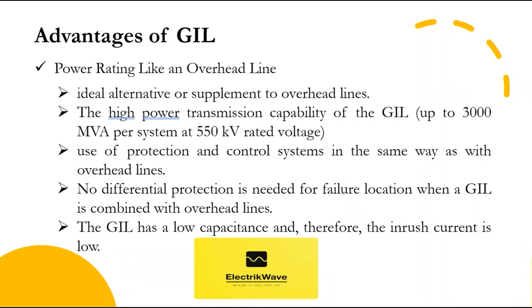GIL has power rating like an overhead line. The GIL is the ideal alternative or supplement to overhead lines. The high power transmission capability of the GIL — up to 3,000 MVA per system at 550 kV rated voltage — allows it to go directly underground in series with an overhead line without power reduction. The GIL also allows the use of protection and control systems in the same way as with overhead lines. No differential protection is needed for failure location when a GIL is combined with overhead lines. The GIL has a low capacitance and therefore the inrush current is low.